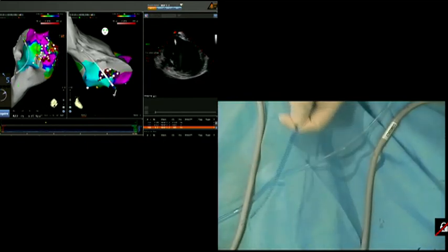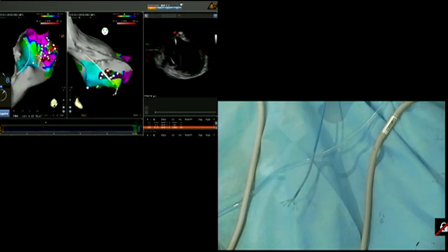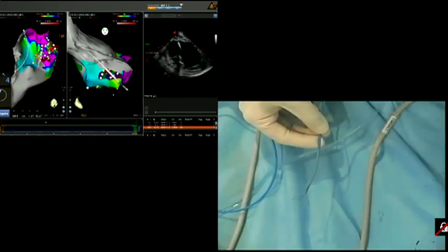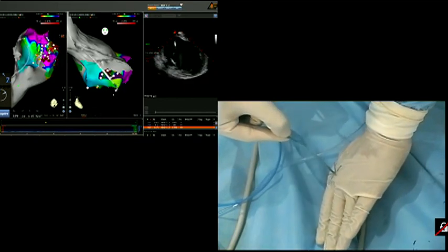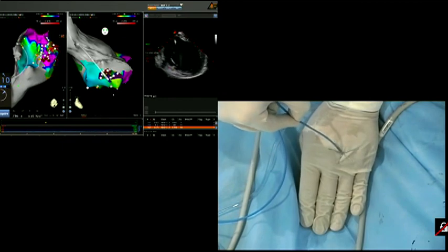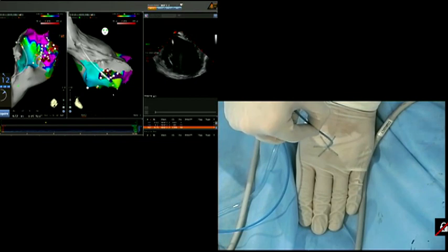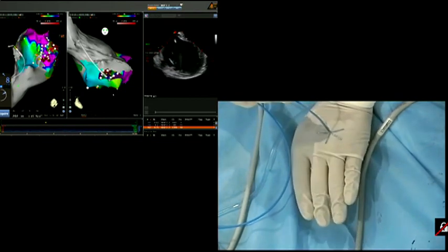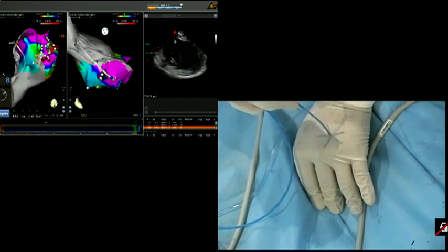Magnify, probably here you are able to see the pentarray. Yes, they have 1 millimeter electrodes, so surely you will get very good images. This is the shape. Yes, because you record from a larger area at the same time.